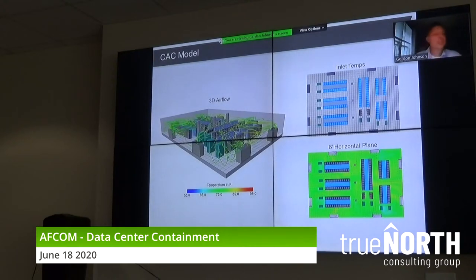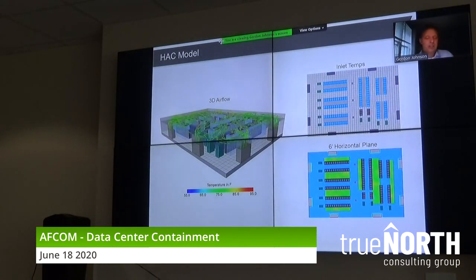Now, what happens if I decided to do hot aisle containment? Remember I said I had a return plenum ceiling? So look on the left, there's a translucent hot aisle or return ceiling. I put ceiling grills in. I've now moved my containment from the cold to the hot aisle, opened some tiles above the ceiling. All of the hot air comes up, over through the ceiling, back into extension hoods that have been placed on the CRAH units.